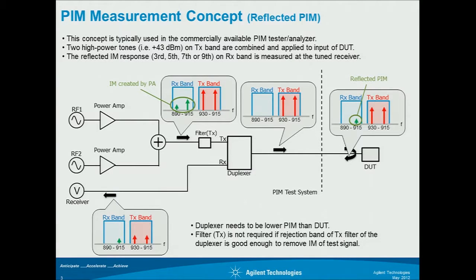The key part of this measurement is actually the duplexer. We have to have a lower PIM duplexer than the actual DUT. If the PIM of the duplexer is higher than the DUT, we cannot measure the PIM of the DUT.